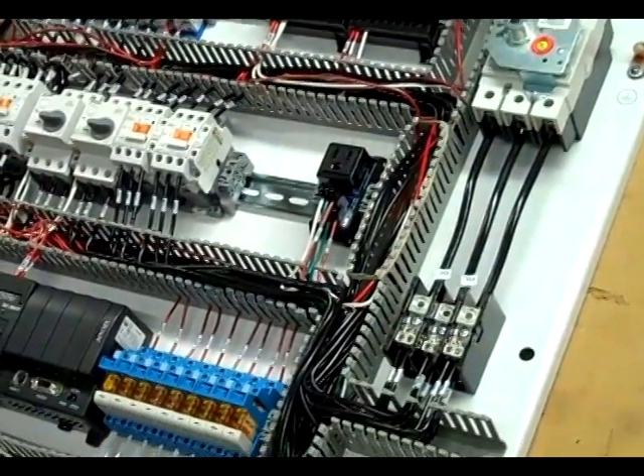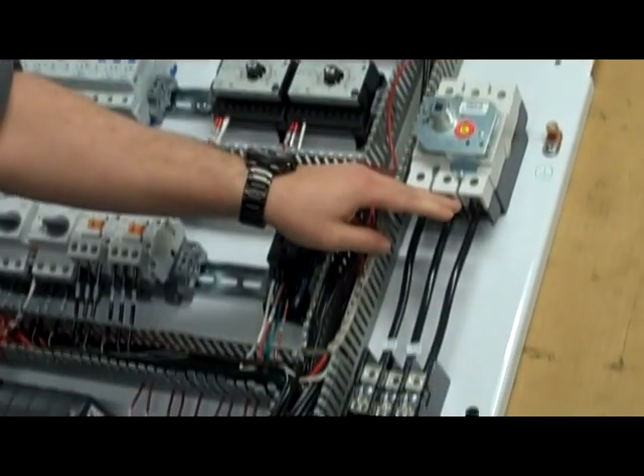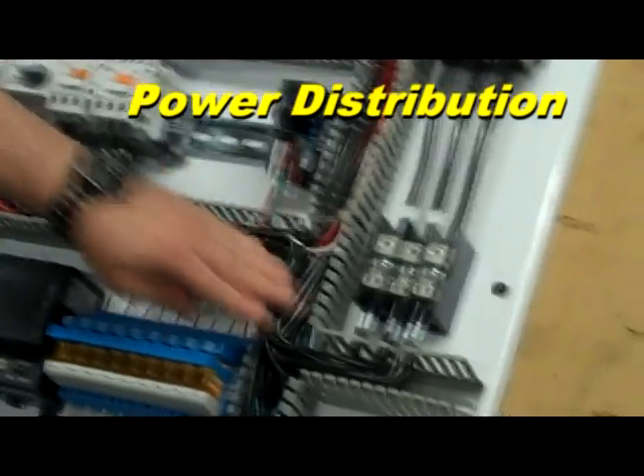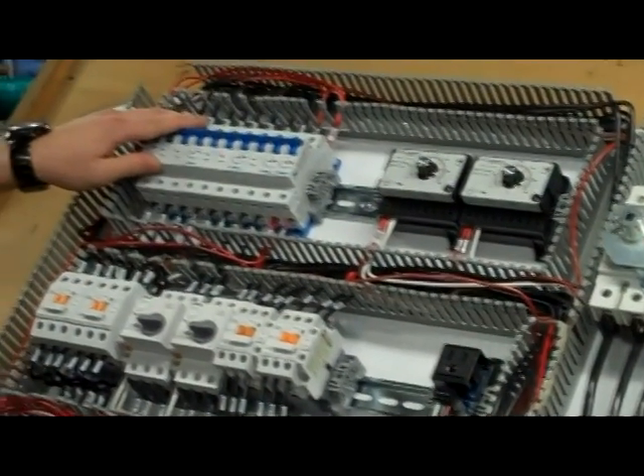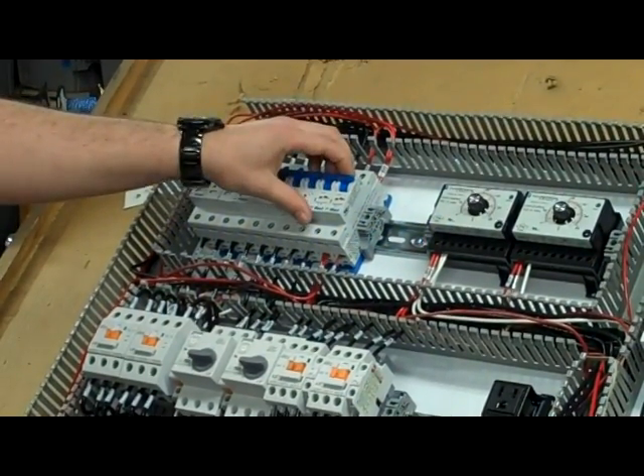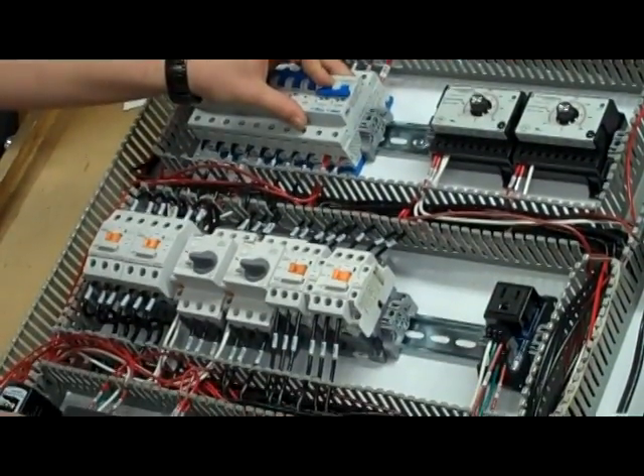Let's look at a typical layout and components of a PLC control panel, starting with the main circuit breaker for disconnecting power from the high-voltage 480-volt feed. This is connected to the power distribution block that separates power for the multi-tap conductors that feed the circuit breakers for each individual heater connection. Here, also, are the control circuit breakers for disconnecting power of the 120-volt components.